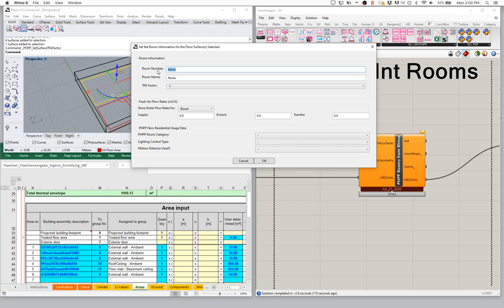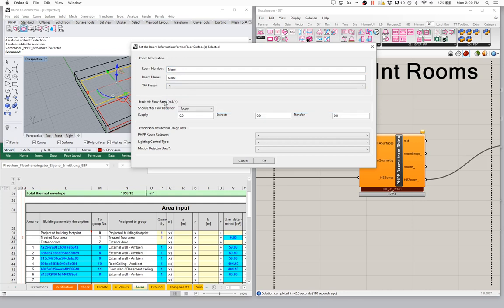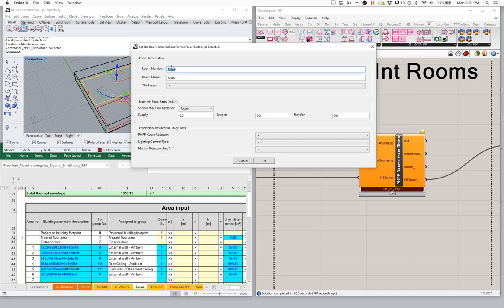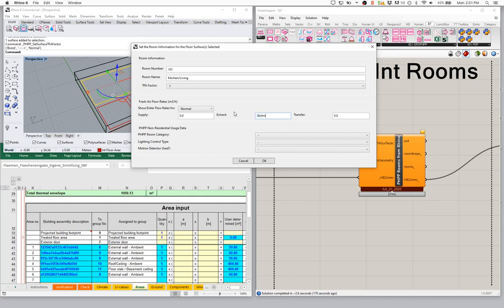It's going to ask me for the room number, the room name, to assign a TFA factor from a list, and to input some information about the fresh air ventilation. Let's say this is room 101, the kitchen living room, with a TFA factor of one because it's main living space. We have to apply some fresh air ventilation flow — if it's a kitchen at normal flow rate, I probably want something like 36 cubic metres per hour of continuous extract.